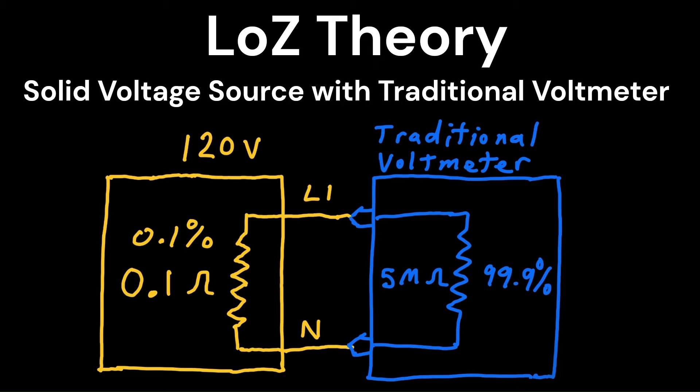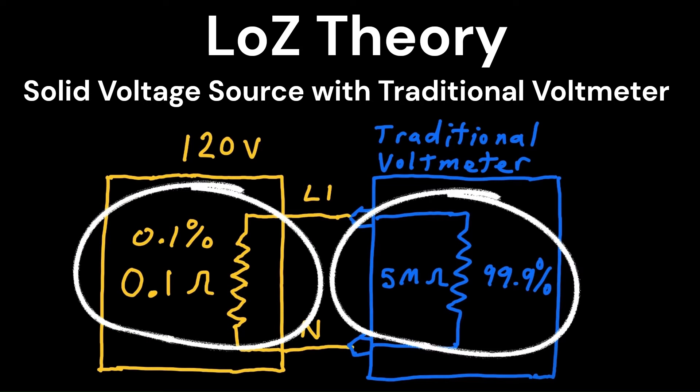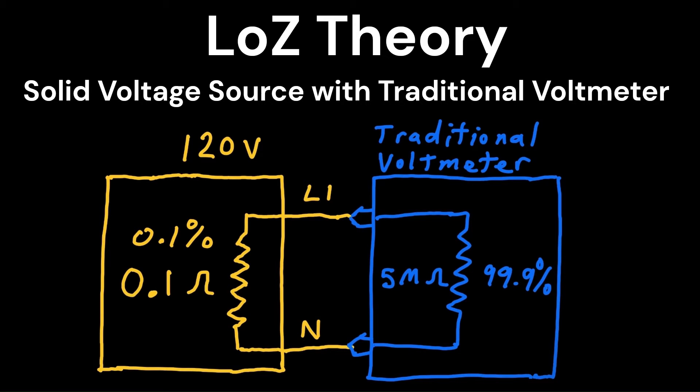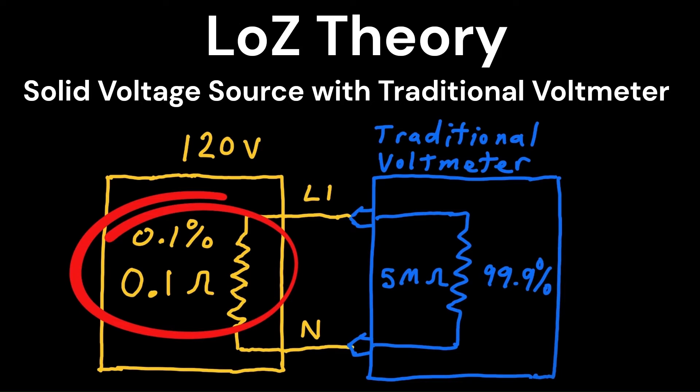So a little about low Z theory. Whenever you read something with your meter, you create a series circuit of two loads where the original voltage source is roughly split up among the two loads. The highest resistance gets the most voltage whereas the remaining resistance gets the difference.